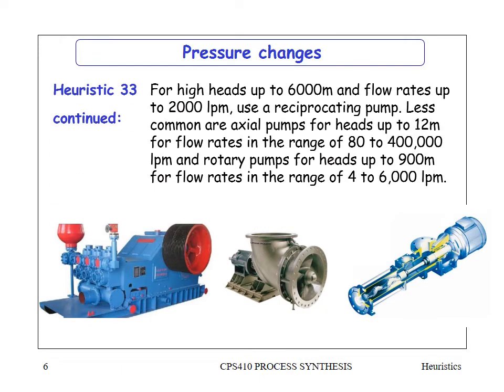For high heads up to 6,000 meters — that's 600 bar pressure — and flow rates up to 2,000 liters per minute, which is a relatively low flow rate but extremely high head, use a reciprocating pump. That is the illustration on the left-hand side. A reciprocating pump has pistons that compress the liquid and push it up to a higher pressure.